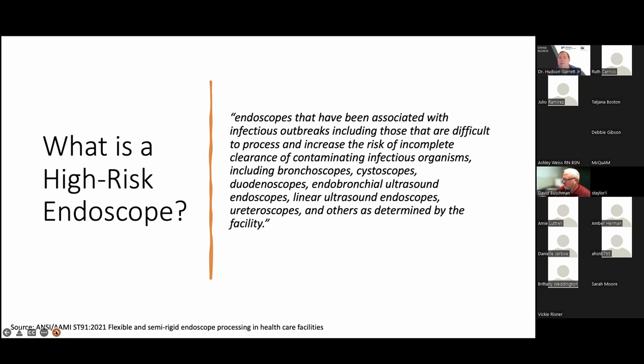It could get a little wonky to try to interpret whether or not it's still a high-risk device, because they really classify it based on the device versus the patient. Certainly if you're using certain devices in different anatomy, like an ERCP, you're moving into a more sterile body area where there's a broader risk for contamination, dragging organisms from the non-sterile area into the sterile area. That poses a risk. So I have mixed emotions about this proposed definition, but it does highlight that all these devices, especially those not single-use, can be high-risk devices.